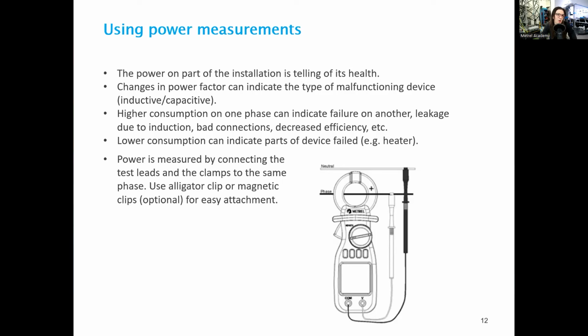If we have trouble with capacitive devices, or even if we have capacitor banks present in the installation, it can cause a very distinct drop in power factor. However, if we lose some inductive loads to malfunction, it can change the power factor in the other direction, so increase it. Sudden imbalance between phases in a three-phase system can indicate a problem on one of the phases, some malfunction, which will cause the other two phases to draw more power.